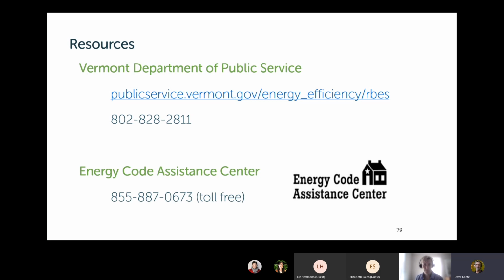In the case of attics, it may not make much practical difference because a good insulation contractor is going to insulate your attic to like R60 anyway. So that probably doesn't matter in terms of insulation requirements. The same is probably true for windows. So if you're replacing windows, you do have to buy windows that have a U value of below 0.3, but you probably just do that by accident because all the window suppliers in Vermont know that you need something below 0.3. So you'd probably have to special order to get something worse than that. So you probably get something good enough just by accident on windows.